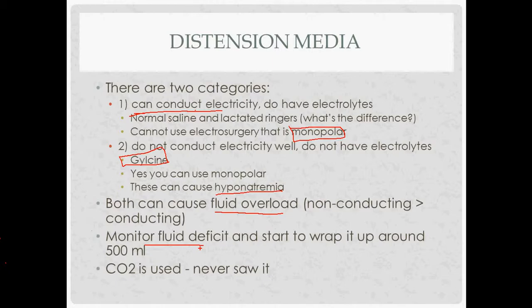The fluid deficit is something you monitor to prevent problems with fluid overload. You monitor the difference between fluid going in and coming out — the machine keeps track of this. You also need to account for fluid that may have leaked out if the seal isn't very good, usually collected in a bag sitting under the patient. If the fluid deficit gets to over half a liter, you want to start thinking about wrapping the procedure up or possibly stopping. CO2 is another distension media used, mainly for diagnostic procedures.